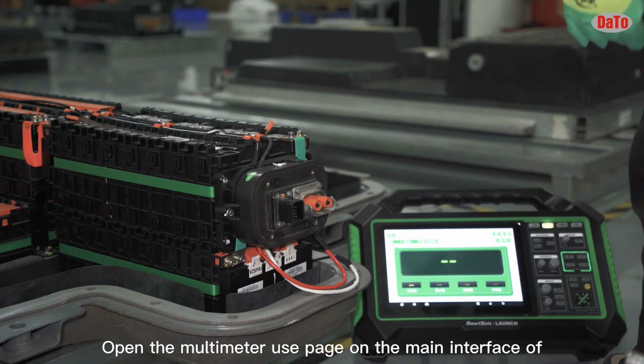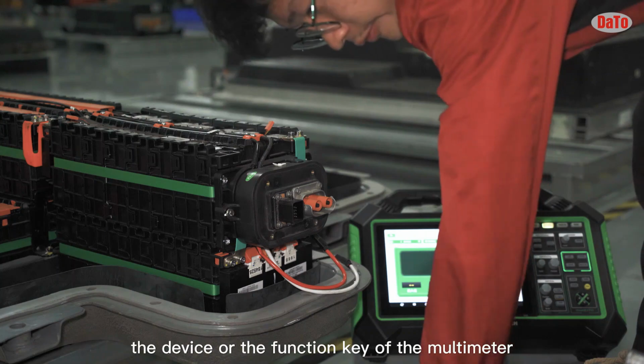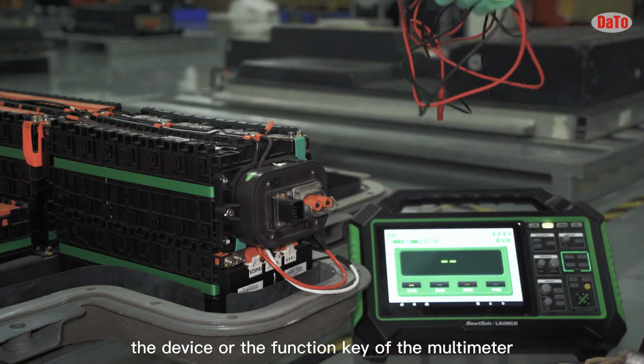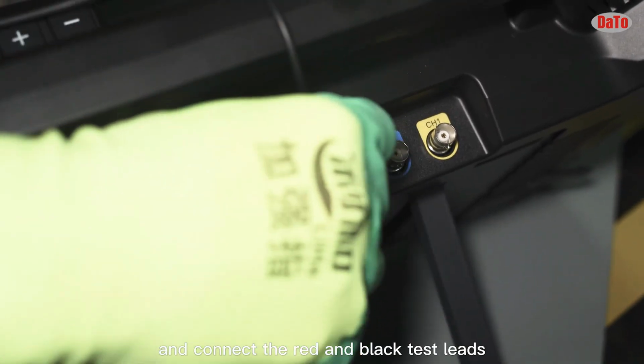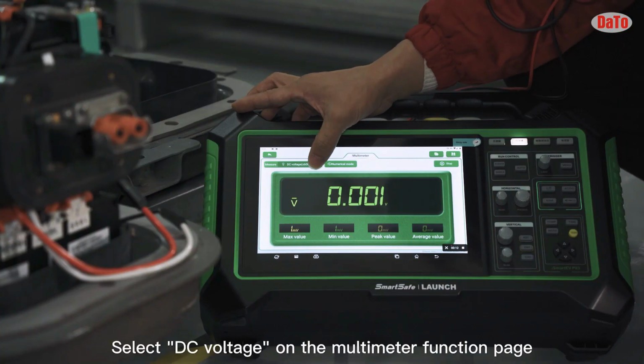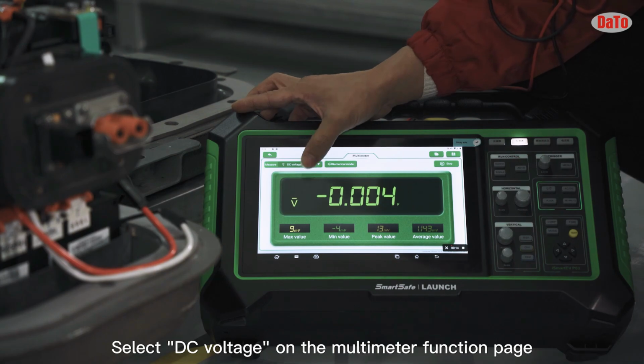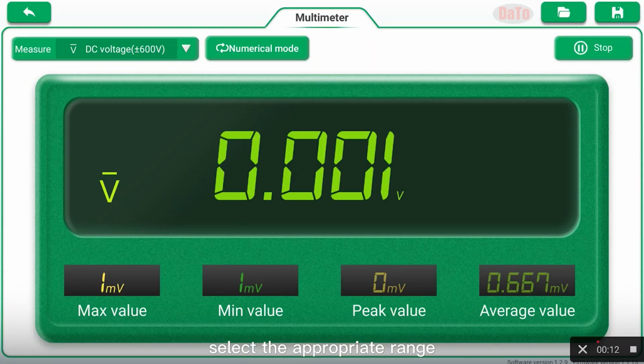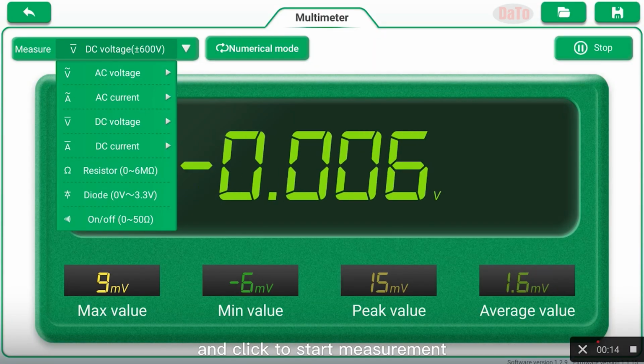Open the multimeter use page on the main interface of the device, or use the multimeter function key, and connect the red and black test leads. Select DC voltage on the multimeter function page, select the appropriate range, and click to start measurement.